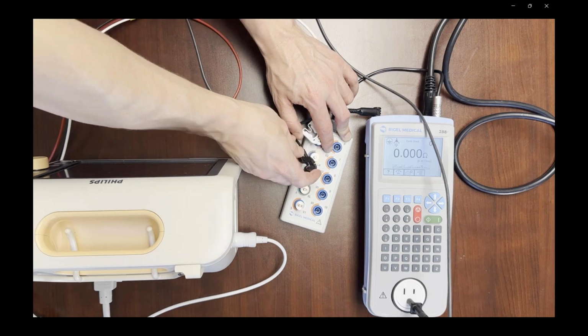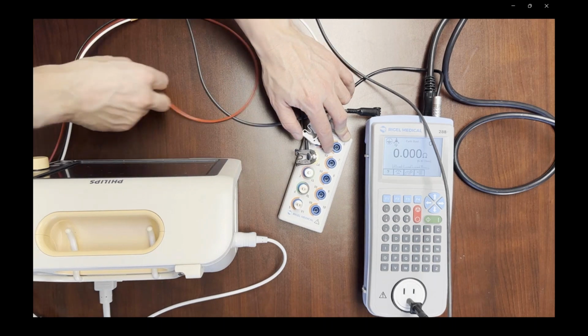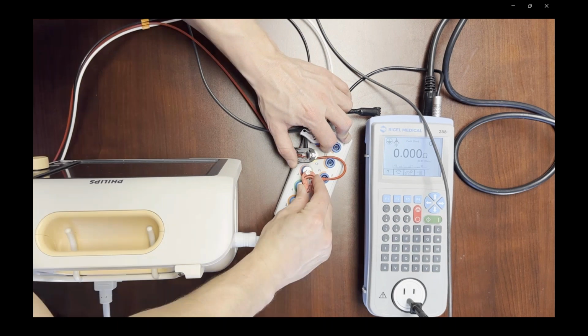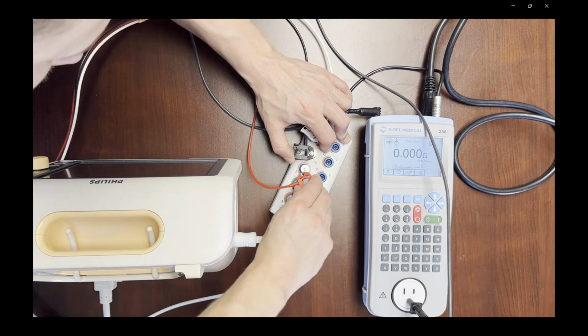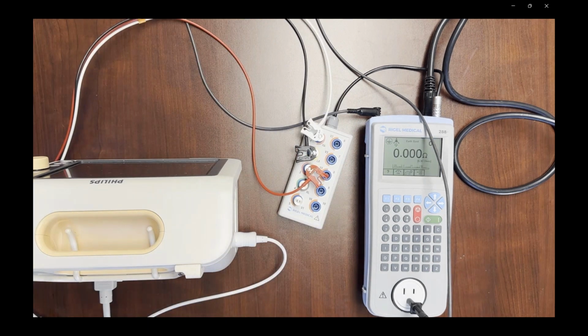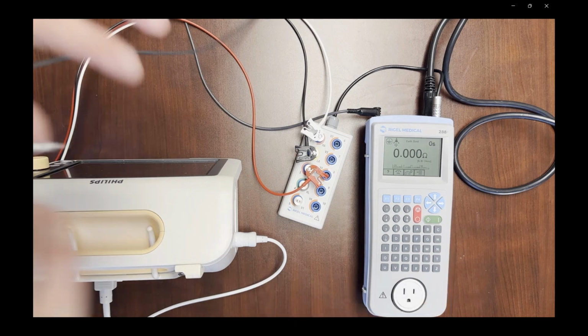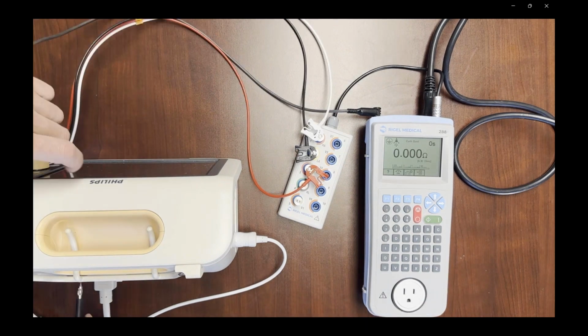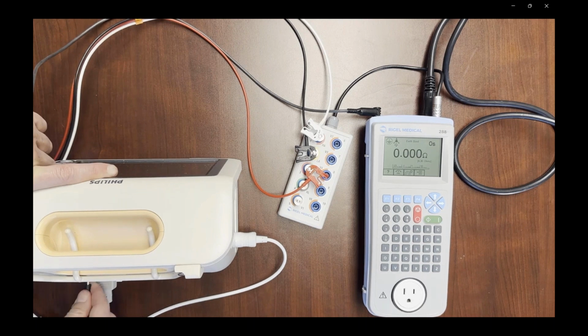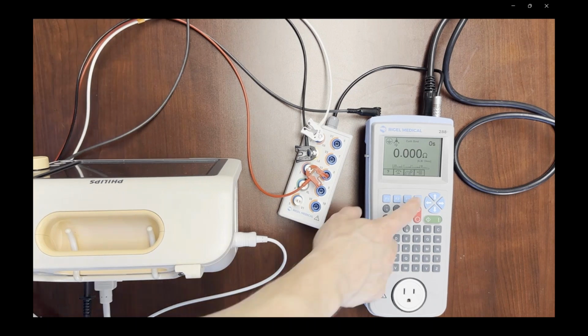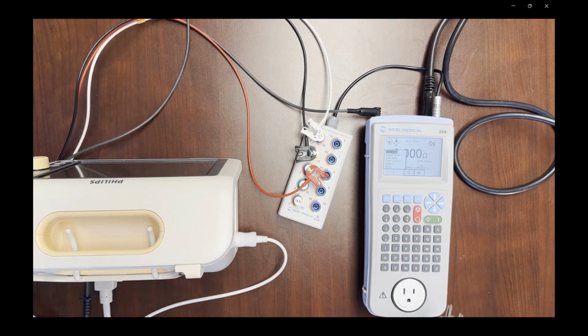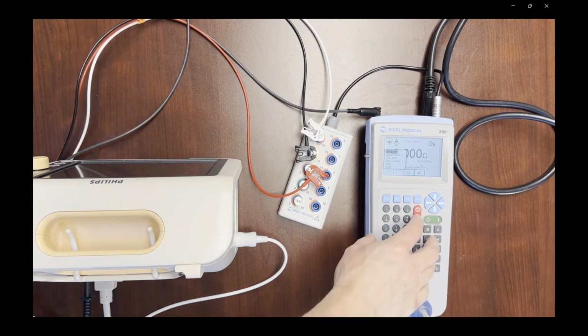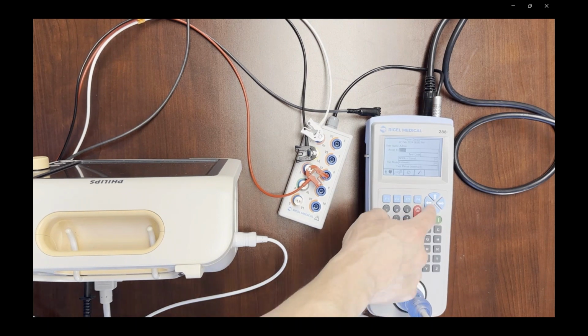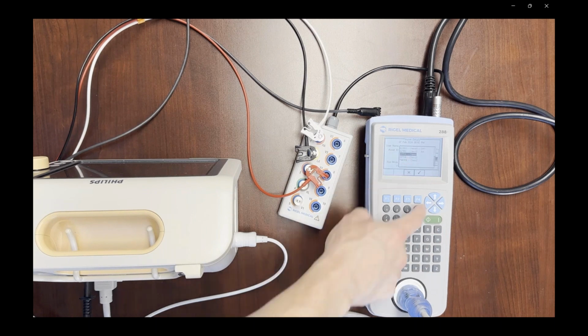In this example, the earth bond lead is running back to the DUT socket. So you can use your own test leads. Just make sure that they're zeroed out before performing a test. So that's been zeroed before. Connect it to the rear of the device under test. Device is plugged in, auto mode, in the same way that I keyed in the asset ID, NFPA 99 class 1.